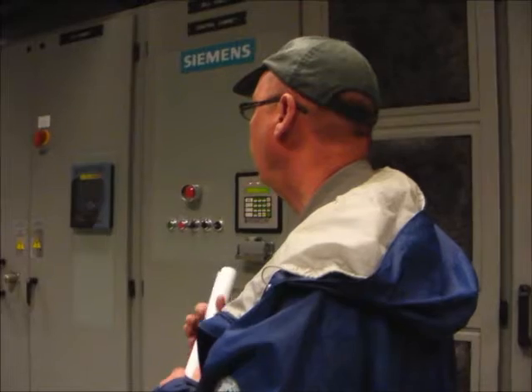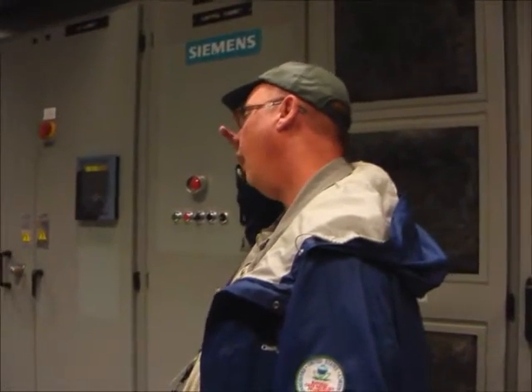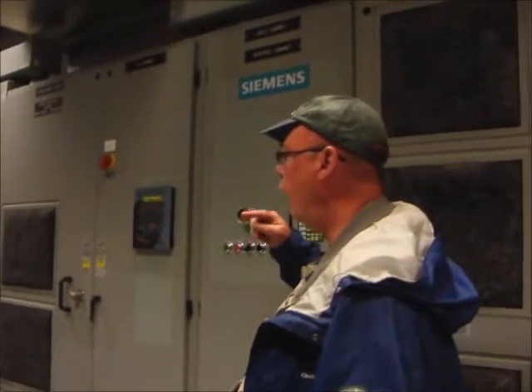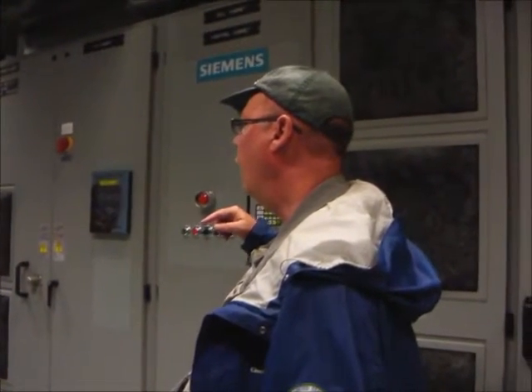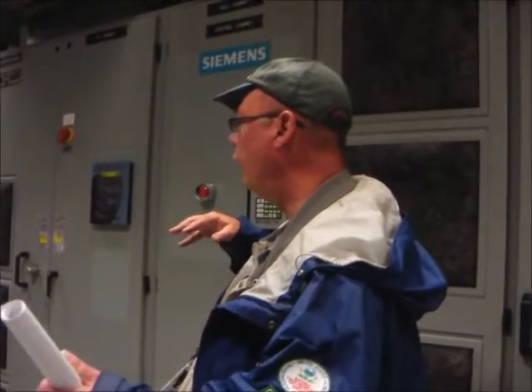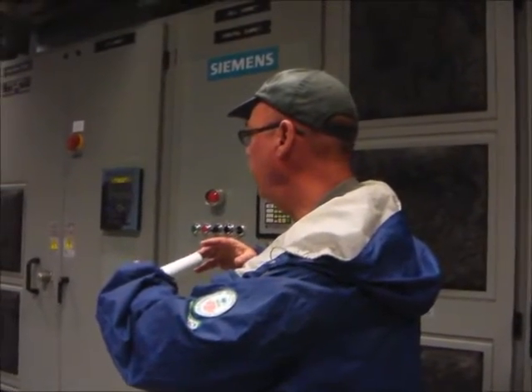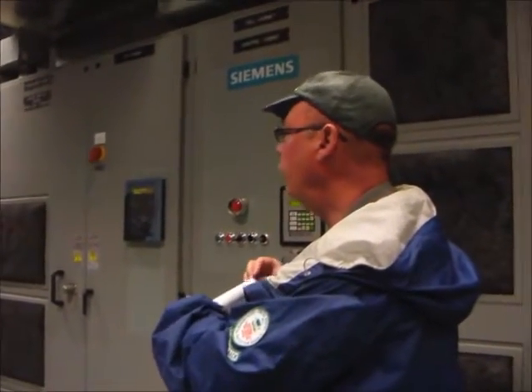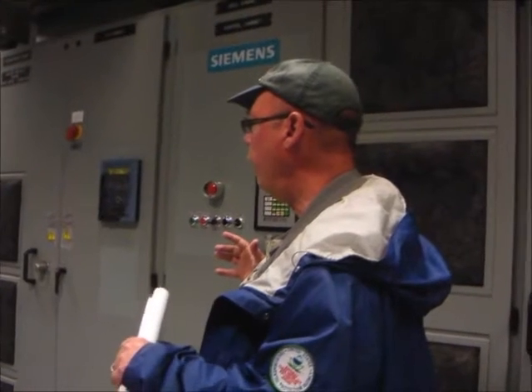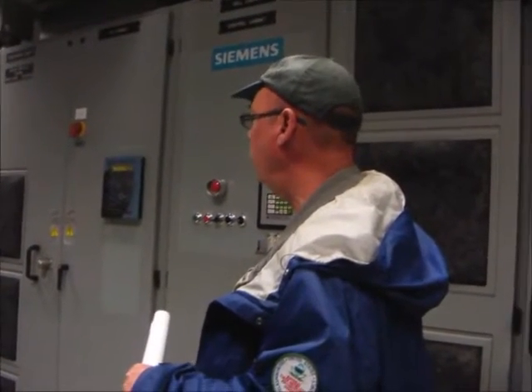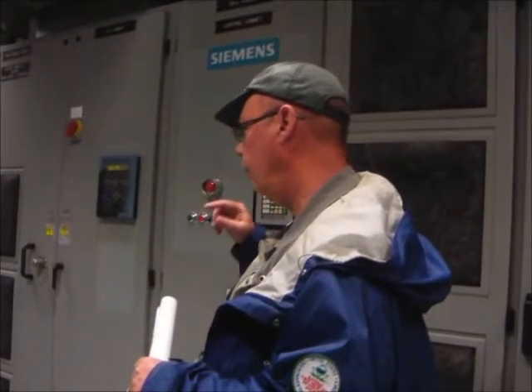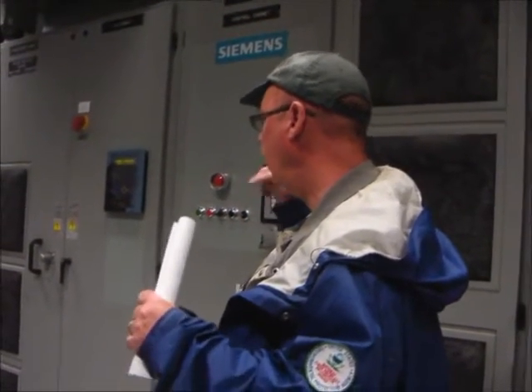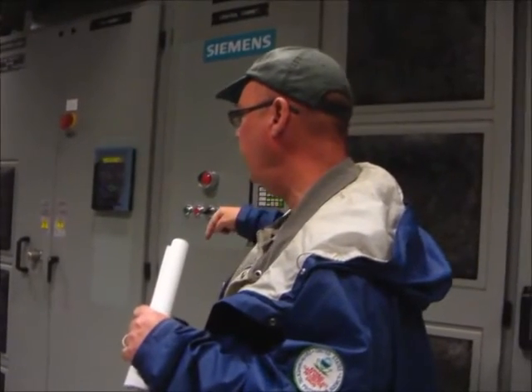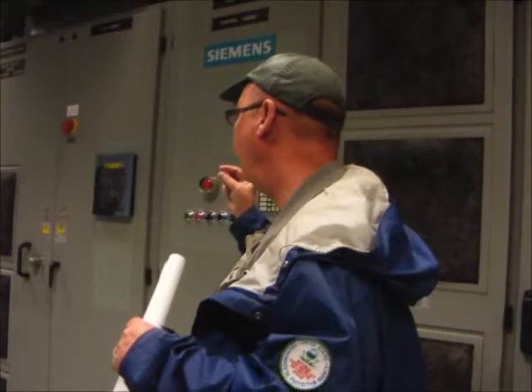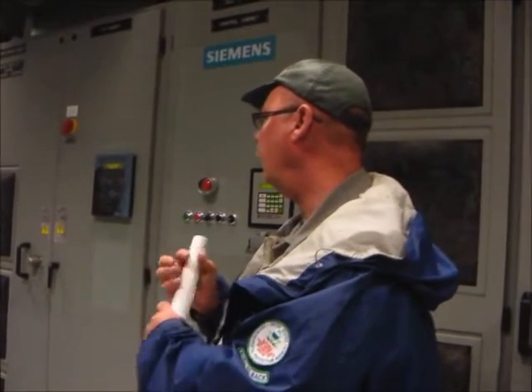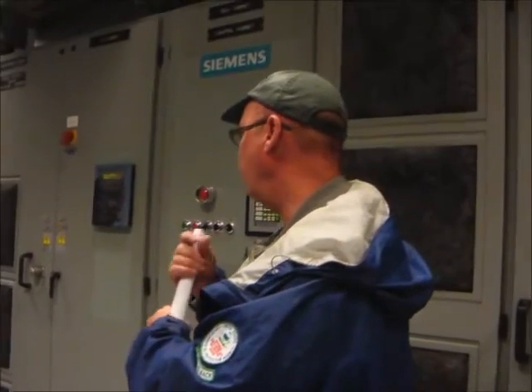When you say PLCs, is that different than SCADA? Yeah, PLCs are the programmable logic controllers. And the SCADA terminals are actually the windows into the PLCs themselves. The SCADA terminals really don't control any part of the plant, but they do tell the PLC what to do. So if we want to increase the flow to the plant, we can do that through the SCADA terminal. It goes and talks to the PLC, it says ramp pumps up. Small difference, but a little bit. A lot of times we'll need to take the SCADA system down for some maintenance.